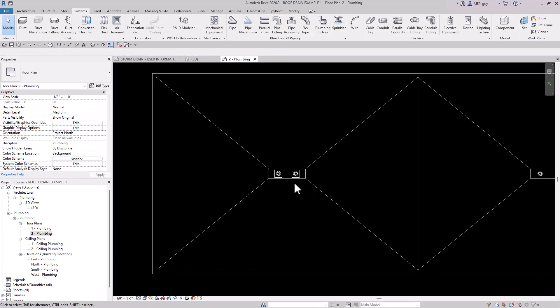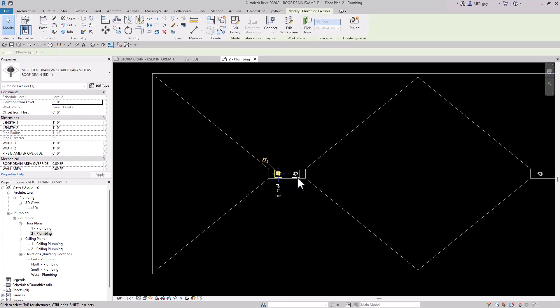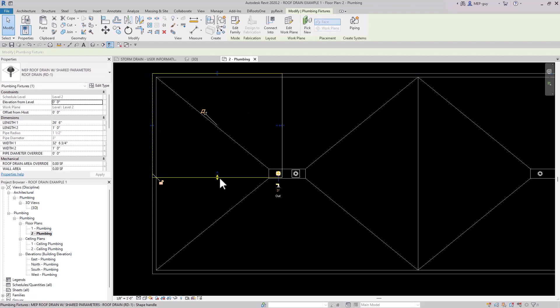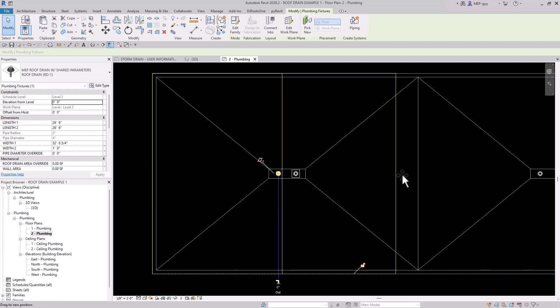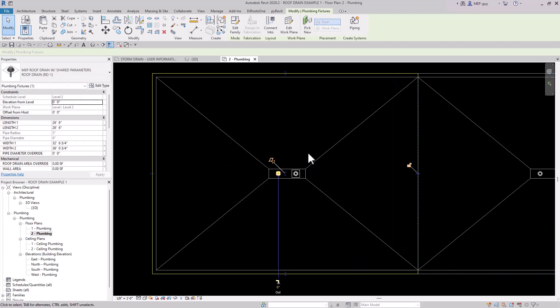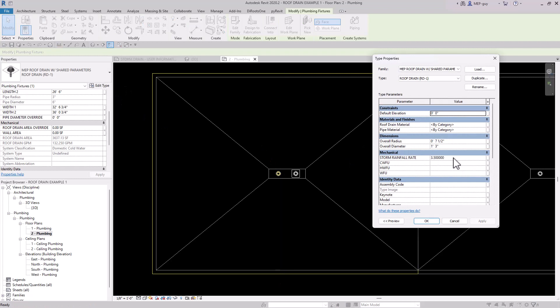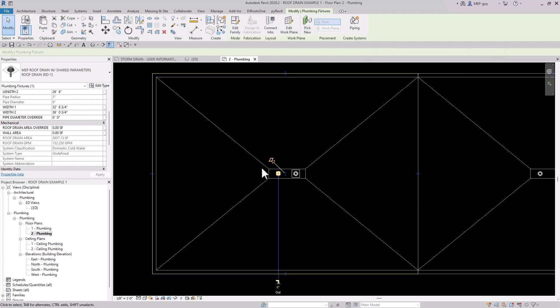Let's size the storm system. I'll click on the roof drain and drag the grips to cover the area of the roof — dragging up, across, and down to create a rectangle around the roof area associated with this storm drain. You can see in the Properties panel that the roof drain area is being calculated: 3,637 square feet, which converts to 132.2 GPM. Remember to go to Edit Type and modify the rainfall rate based on your region.